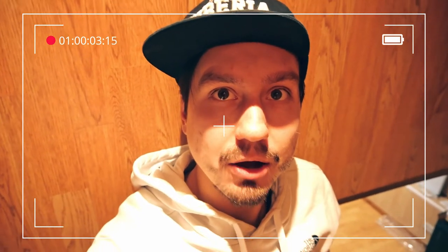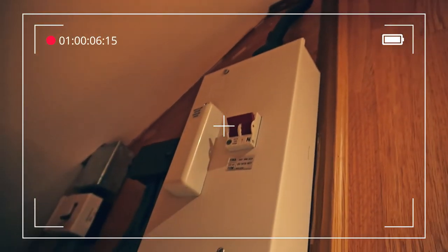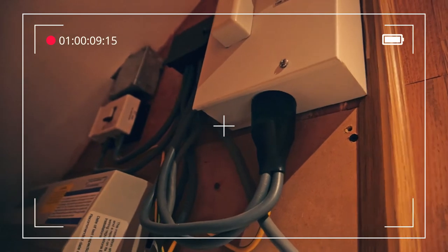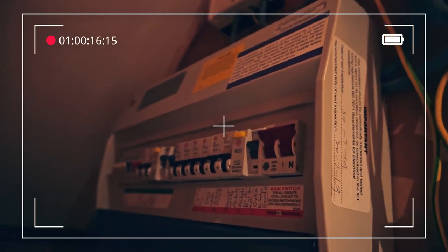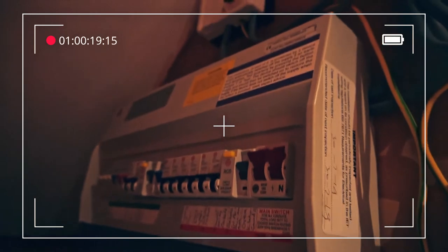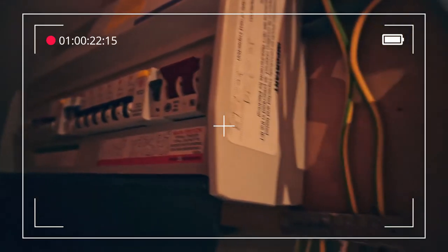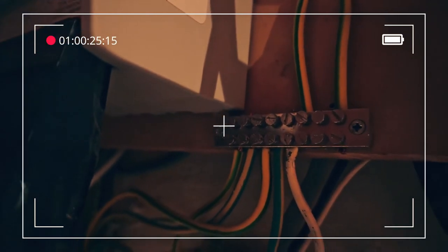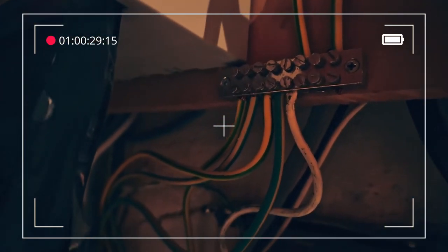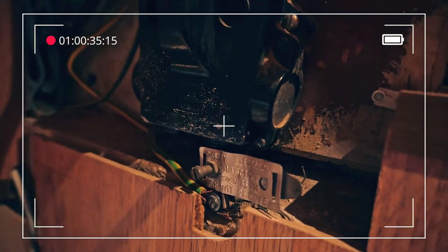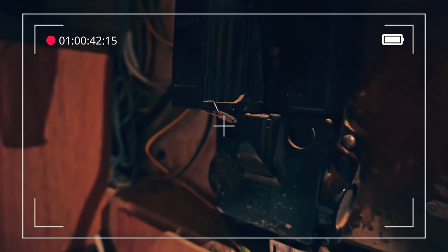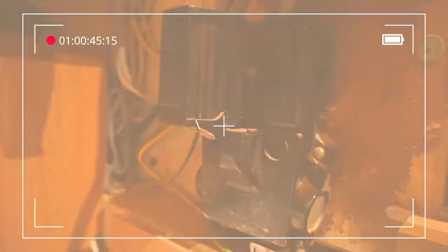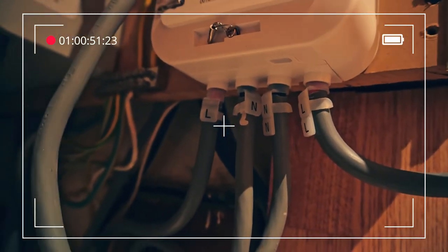For example, let's take a look at the electrical installation in this house. This is where the electricity enters the building and you can see live and neutral wires coming in here and getting into the consumer unit, which contains MCBs and RCDs for the distribution points of the system. Next to it you will see this metal bar, which combines all earthing in the house. Down here you will see the earth electrode. Effectively the neutral wire is combined with the earth at this point, and this type of system is called TNCS. The neutral wire is where the return current for the whole system is coming to.